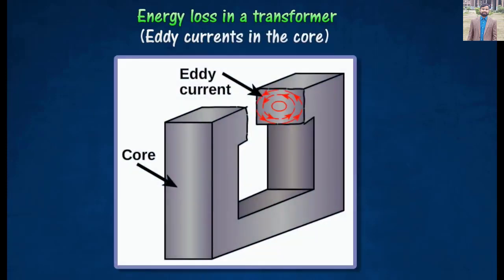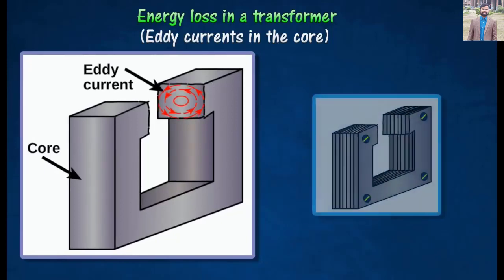occur whenever a transformer is energized and remain essentially constant regardless of how much electric power is flowing through it. To reduce core losses, high-efficiency transformers are designed with a better grade of core steel and with thinner core laminations than standard efficiency models.